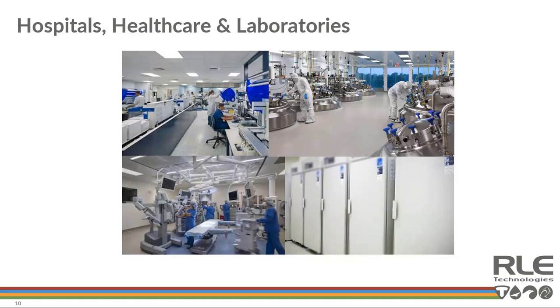We see laboratories with cryogenic freezers incorporating our products into those applications to monitor temperatures within those freezers. They incorporate a 4 to 20 milliamp sensor tied to the FMS, put that sensor in what they call a glycol bottle. So if it opens, it's not an immediate change in temperature - it takes a minute or two, creating that thermal buffer. Certainly we see a lot of applications in those types of environments.